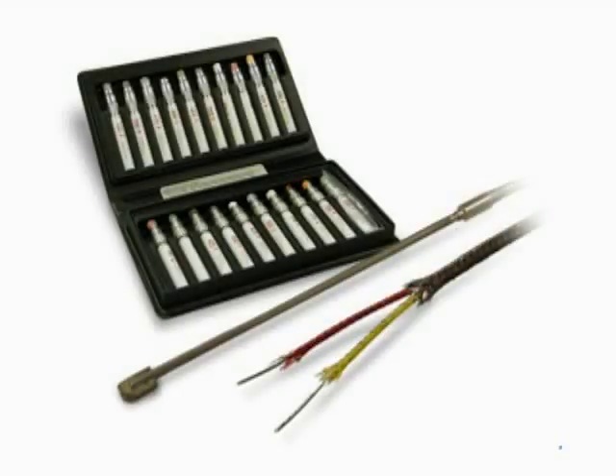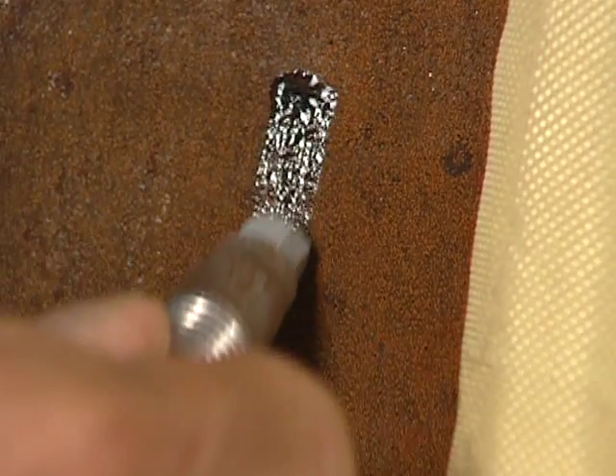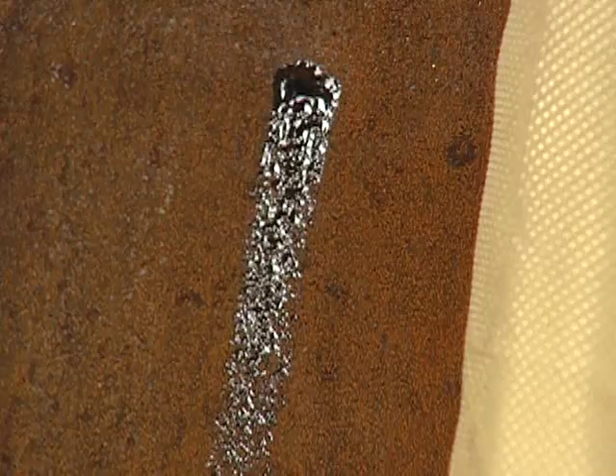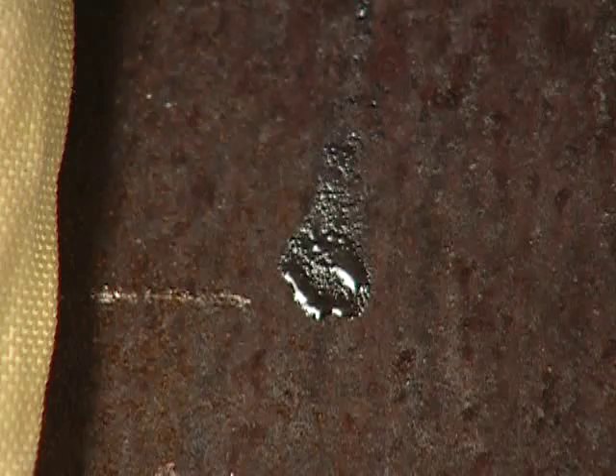There are several tools for temperature measurement that can be used with induction heating. In preheat applications, a traditional Tempilstik can be used. This is a type of crayon used to mark the workpiece, which will melt when reaching temperature. However, this is a highly manual process and is subject to human error. Close monitoring of the melting crayon mark is required.